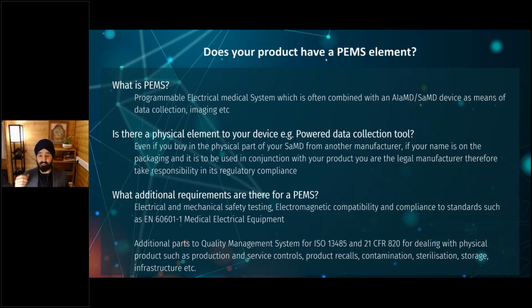You've now got additional testing. You're going to have electrical testing, mechanical testing, electromagnetic compatibility. If you're touching parts of the body, you're going to need to be doing biocompatibility. In addition to that, there's going to be extra parts of your quality management system. You need to not just have design controls for your software part, but you also need to have design controls for the physical element. You're also going to have to deal with production facilities, possibly even sterilization, storage, distribution. And of course, the most important one is an adverse event report.